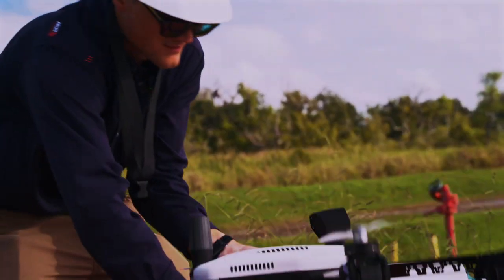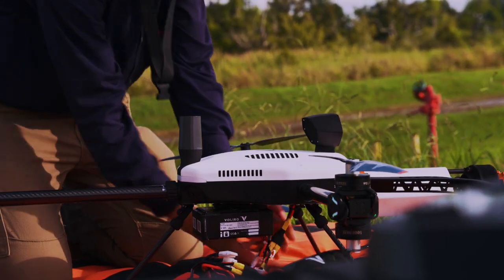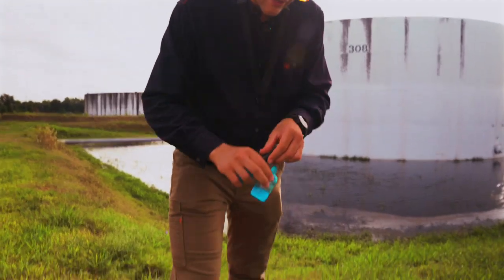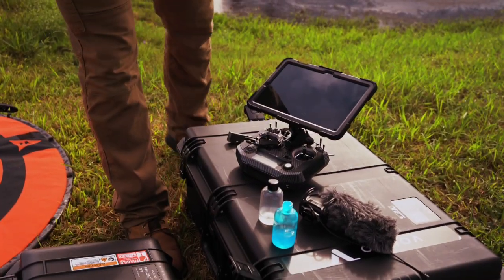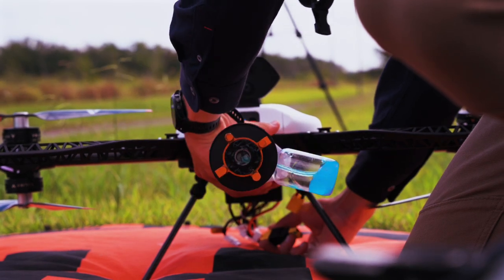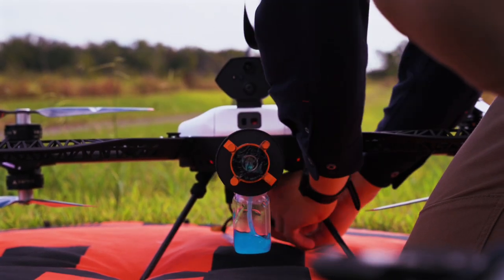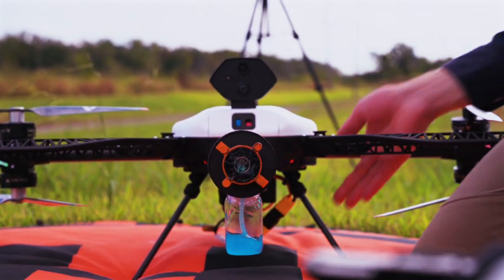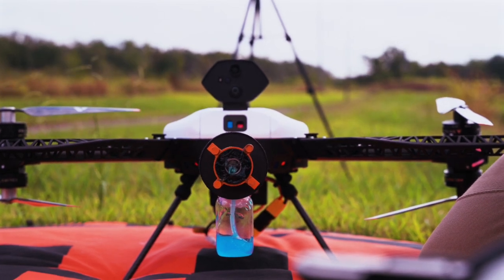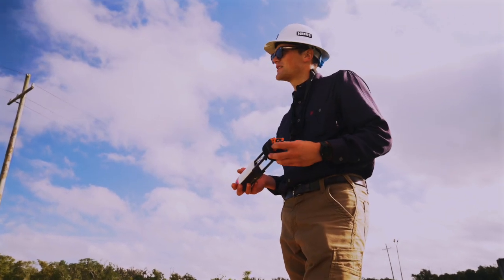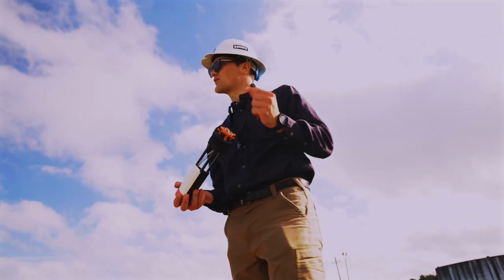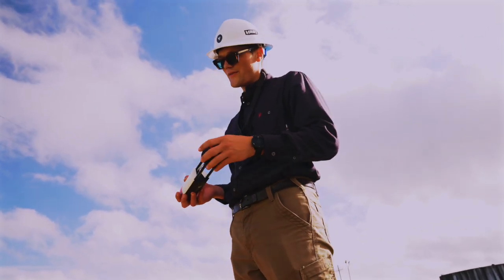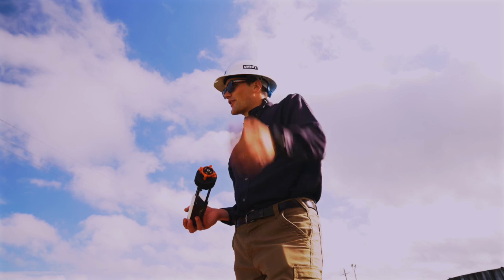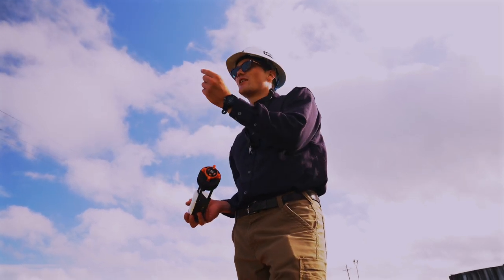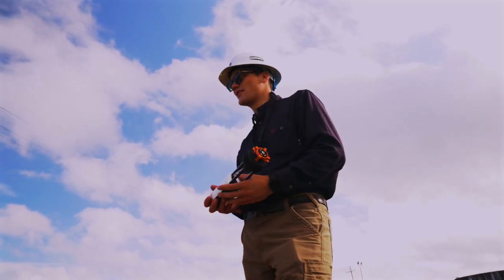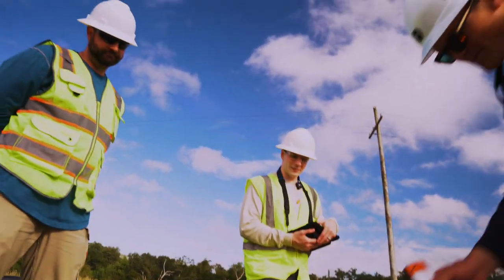Right now we've got 4 payloads. We've got the conventional ultrasonic we're working with right now, and the EMAT, electromagnetic acoustic transducer, which also does wall thickness measurements like the UT - both have limitations and advantages, so it's easy to switch between them. Then we've got the DFT sensor, dry film thickness, used for coating thickness measurements, for when you want to measure the coating rather than the wall thickness. That's quite often used for stuff going offshore, to make sure the coating is thick enough because salt water and salty air will work on that coating.